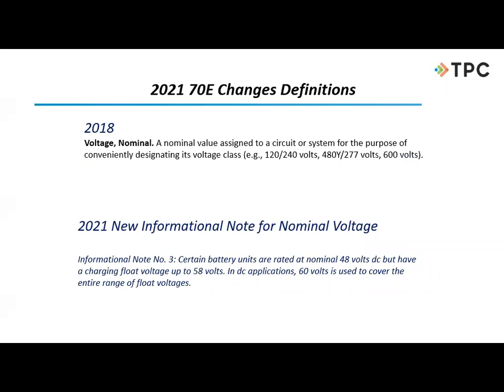Then they came up with something new for the definition of nominal voltage. The voltages you see in 2018 are pretty much all AC systems, our single phase and three phase systems. But then they added an informational note for some DC systems. Some battery systems have a nominal voltage of 48 volts DC, but when charging, that can float up to 58 volts. So in a DC application, they decided to use 60 volts to cover the entire range of those battery systems, and they wanted to make sure we understood why they did that.